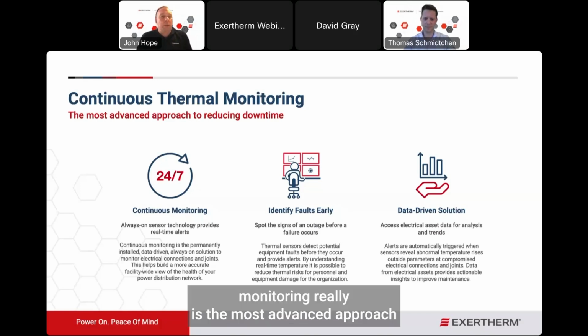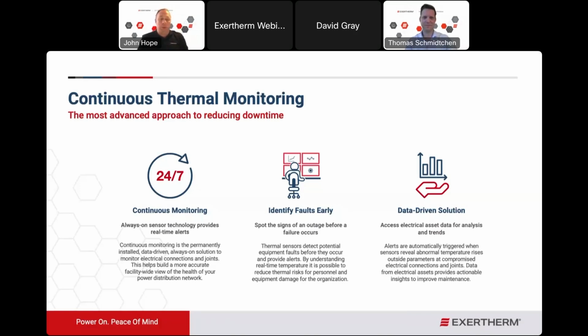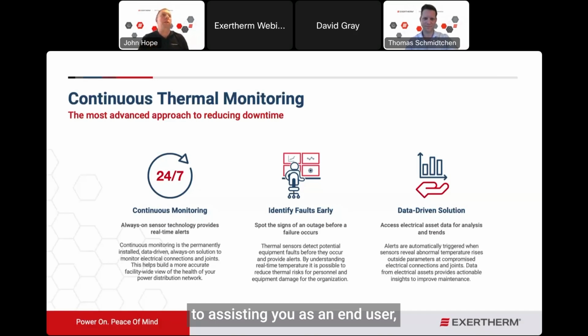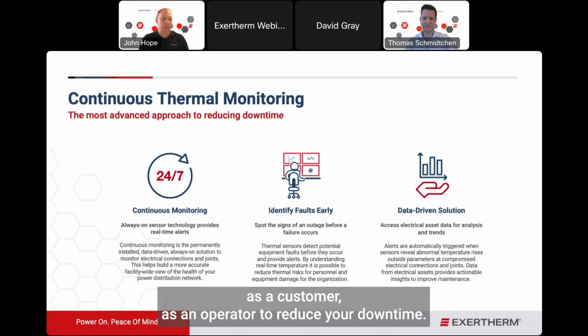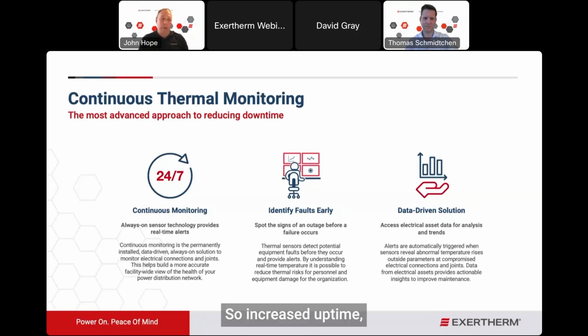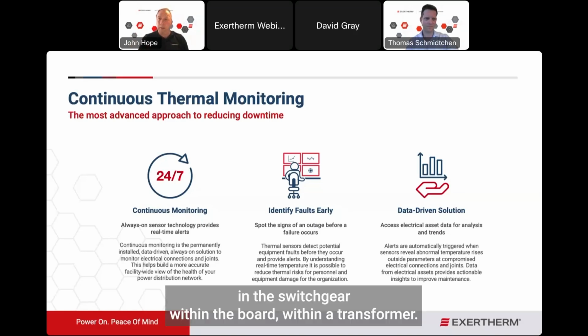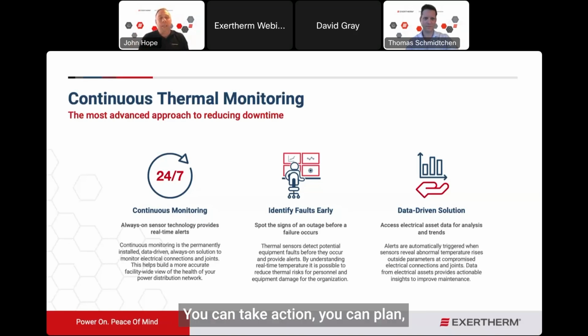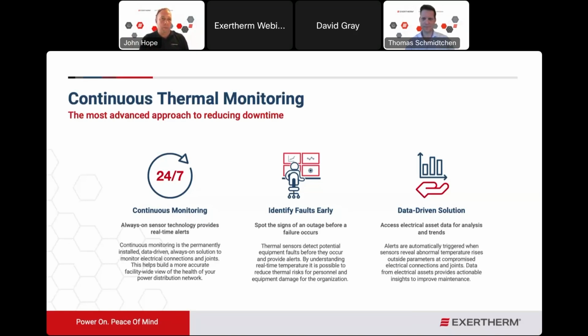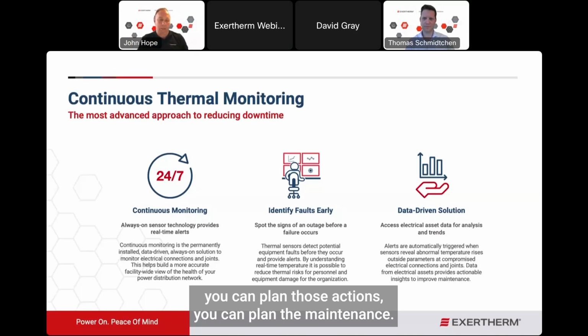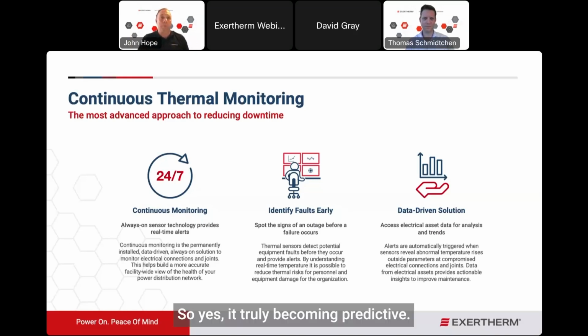So continuous thermal monitoring, really, it's the most advanced approach to assisting you as an end user, as a customer, as an operator, to reduce your downtime. So increase that uptime. You've always got those sensors on. They're providing real-time alerts. You're identifying those faults early. You're getting a very early warning. You've got an issue starting to occur in the switchgear, within a board, within a transformer. You can take action. You can plan those actions. You can plan the maintenance. So, yes, it's truly becoming predictive.